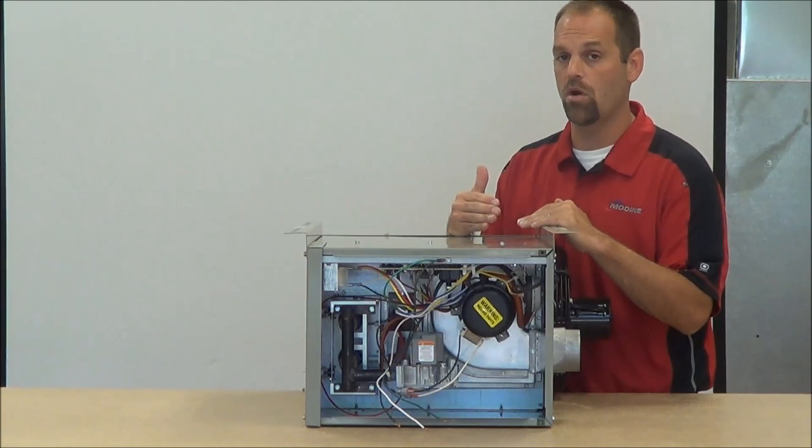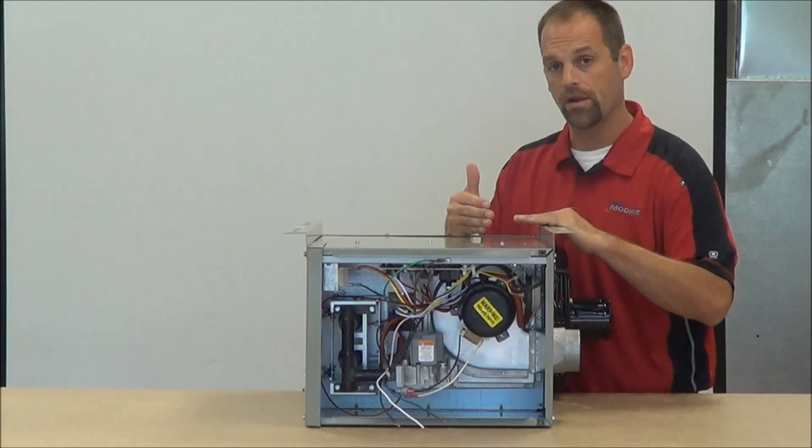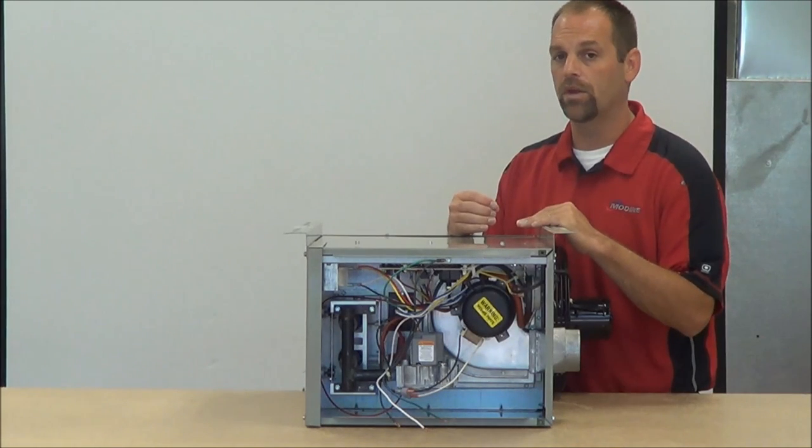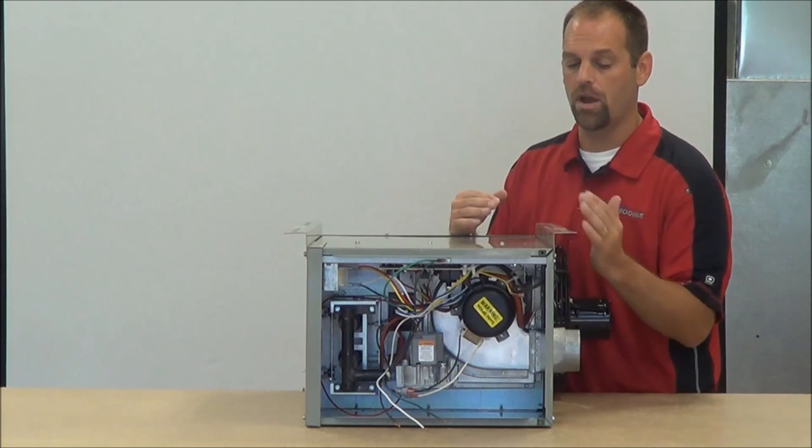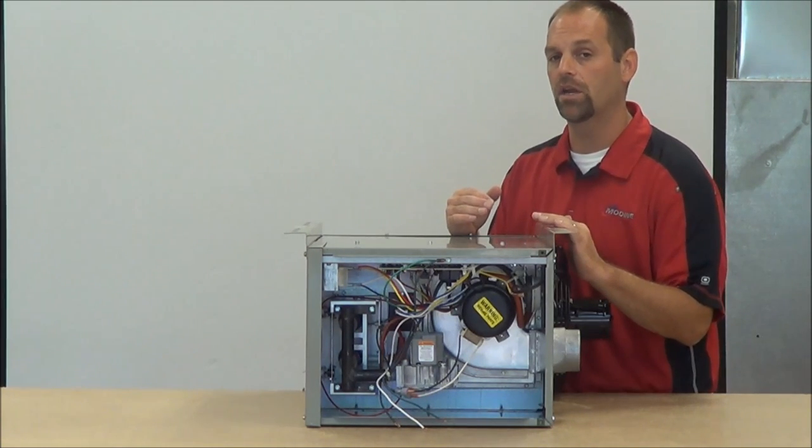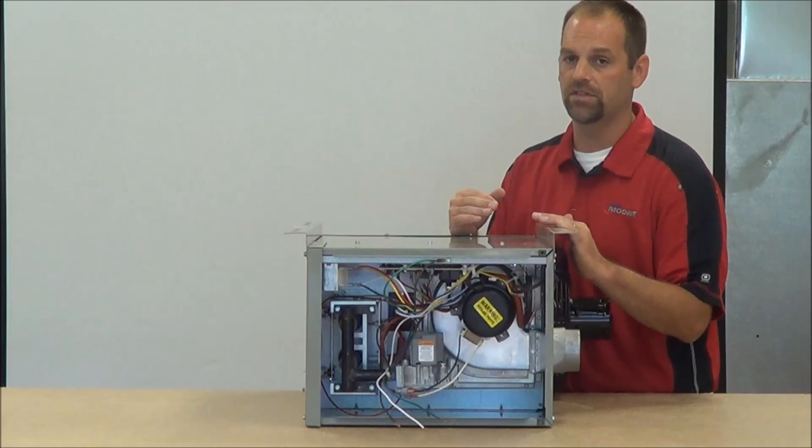Most of the time, the polarity is wrong. You flip those wires. We want to reconnect them. We want to keep them at black to white, black to white. We want to turn our power back onto the unit, and the unit should fire off and take off properly.